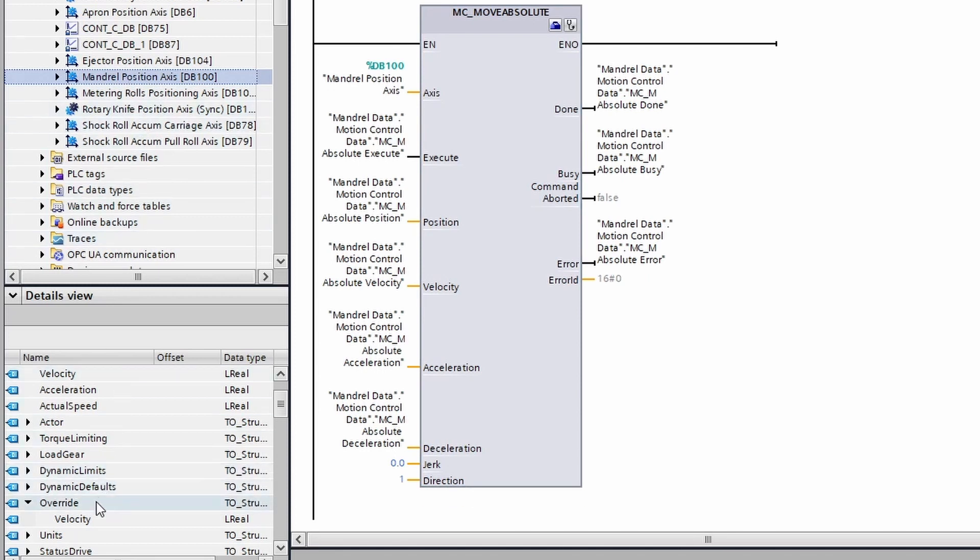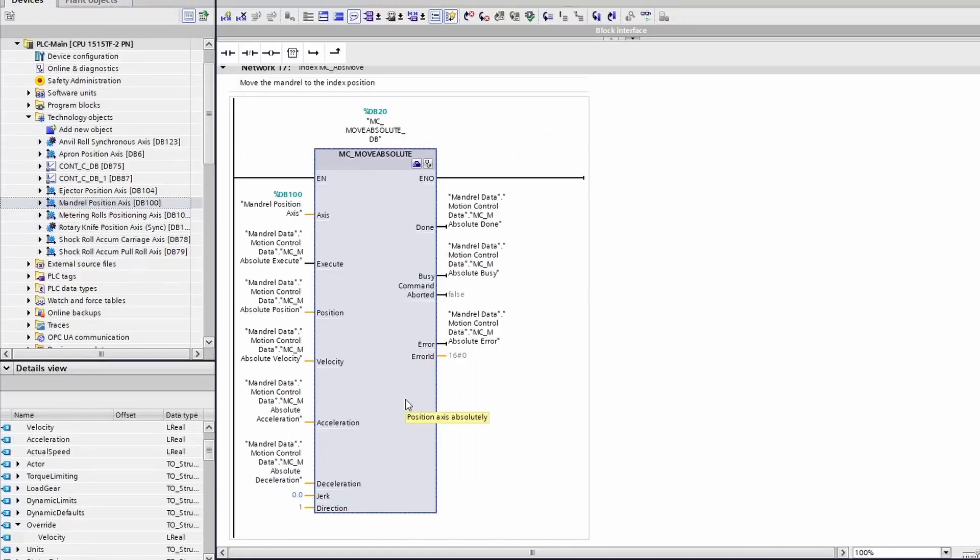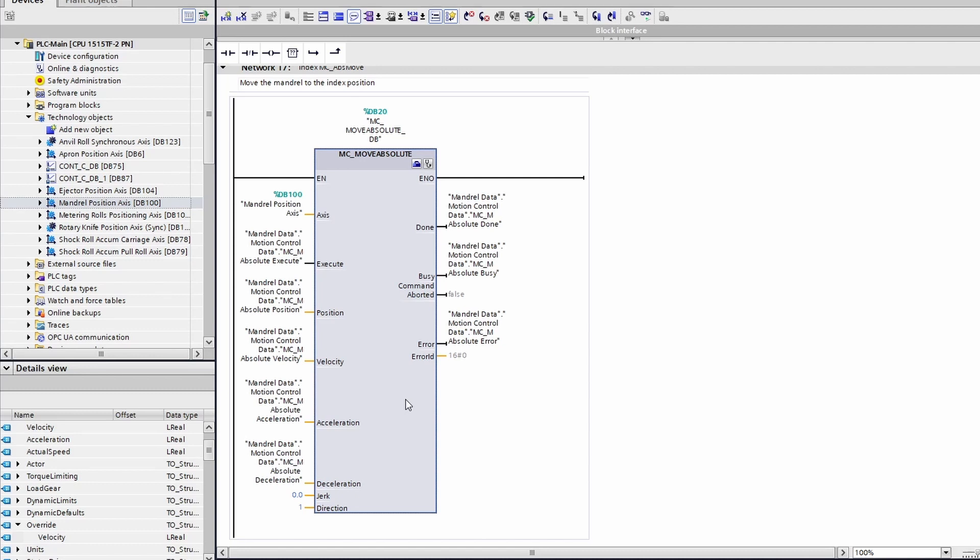Let's talk about the difference between a move absolute and a move relative. If you tell a rotary axis to move relative 360 degrees, that axis will rotate once. If you tell that same axis to do a move absolute to 360 degrees, it may rotate one time, zero times, or one thousand times.